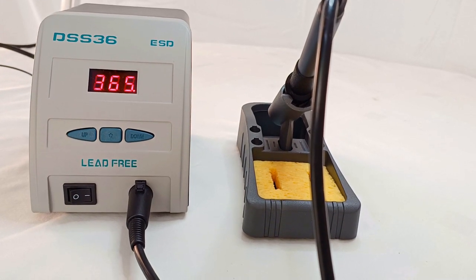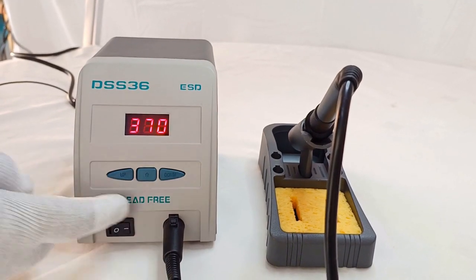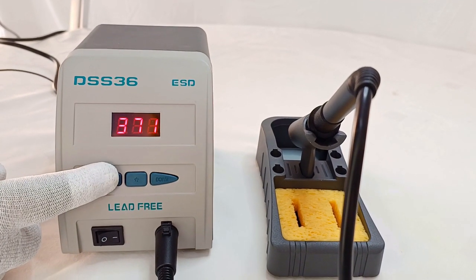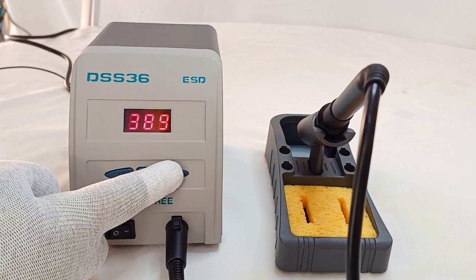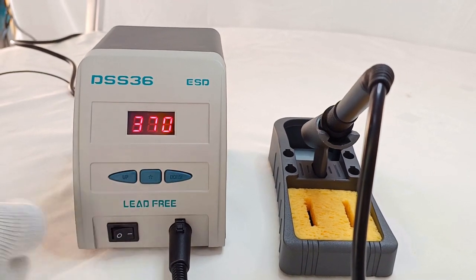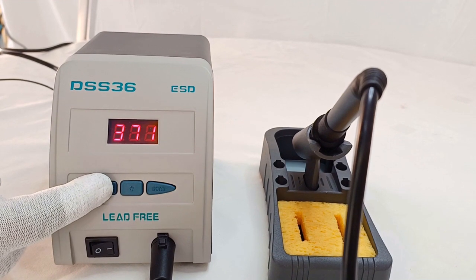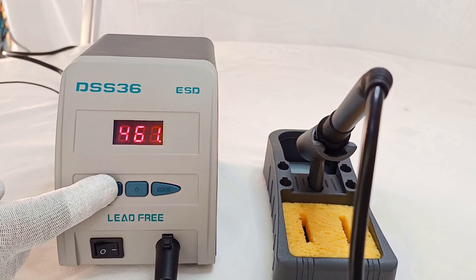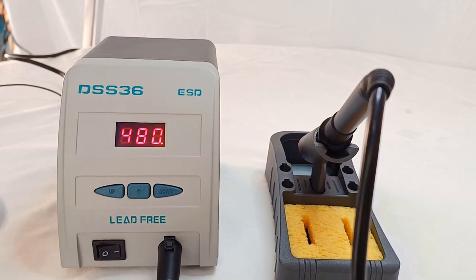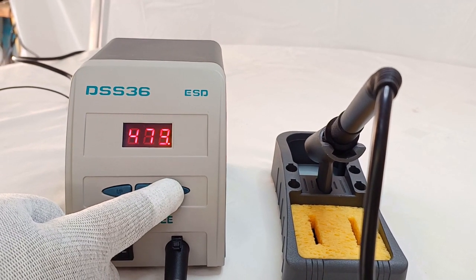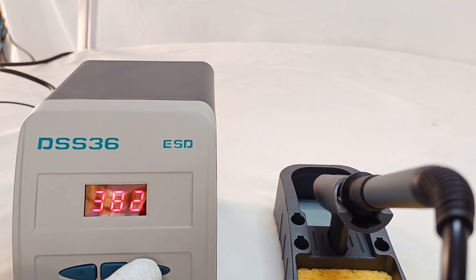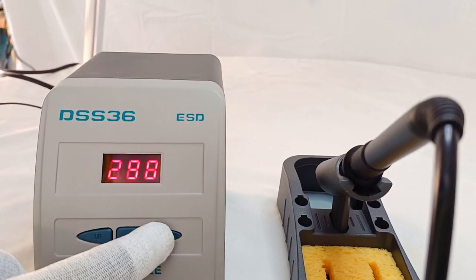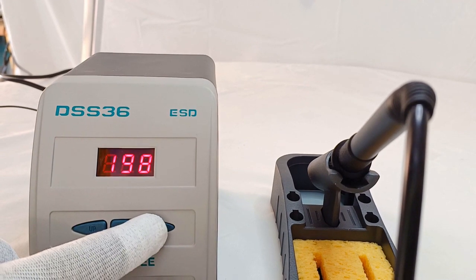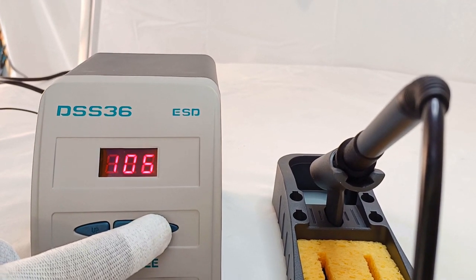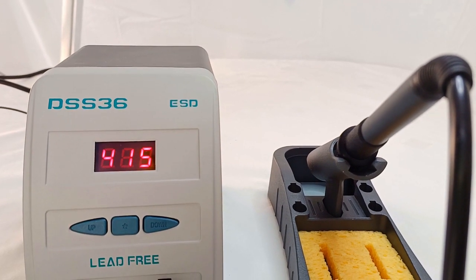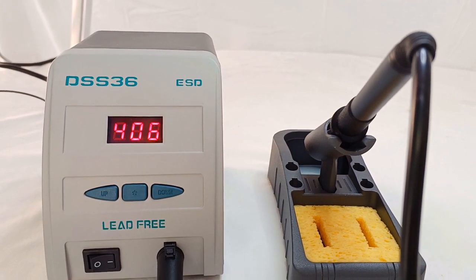There are up and down push buttons on the front panel. Pressing the up button increases the temperature, and pressing the down button decreases it. The upper temperature limit is 480 degrees centigrade. If we keep pressing the up button it will reach the maximum temperature range, and if we press and hold the down button for a few seconds, it will gradually reach the lower limit of 80 degrees centigrade. This is how we can increase or decrease the set temperature.